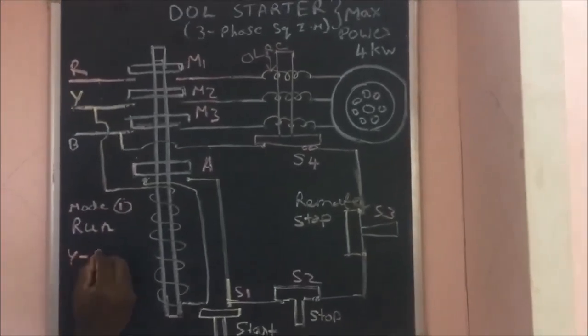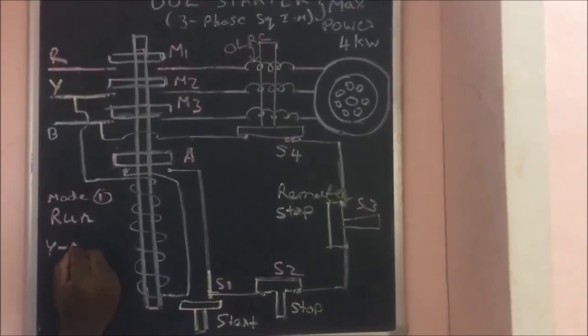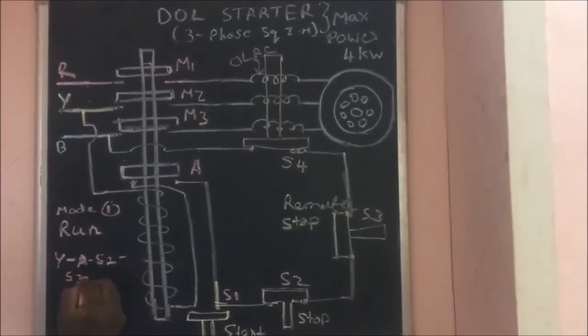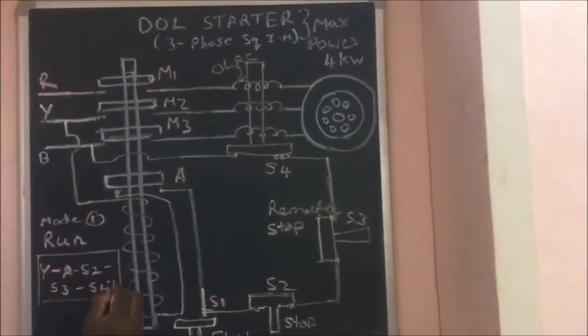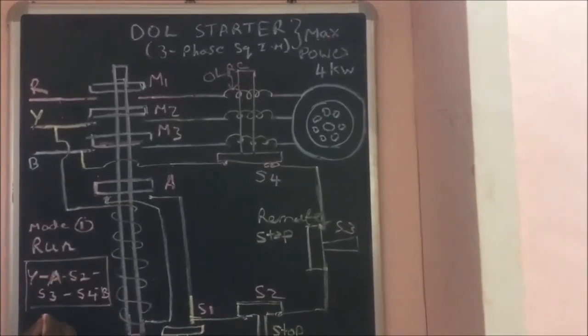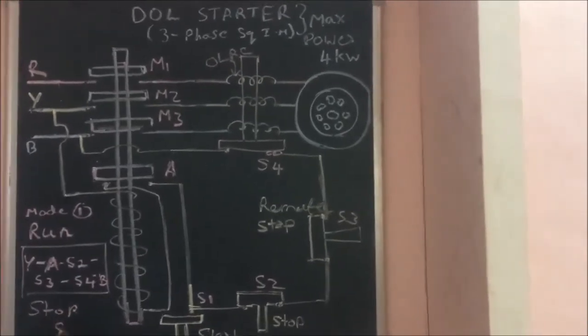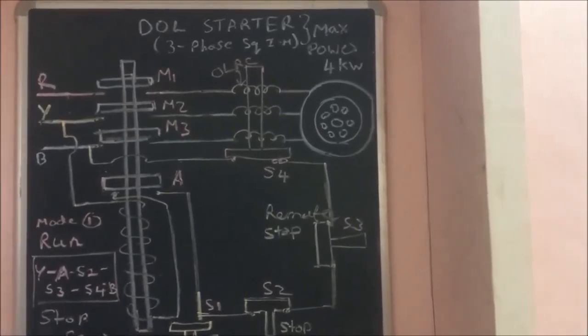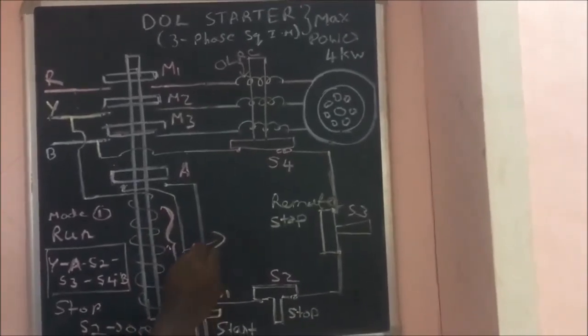In the direct online starter, starting takes place as follows. S1 is the starting or push button — it is the green button. When you push the button, it will close and make contact, and current will flow through Y-phase, A, S2, S3, S4, and finish in B-phase. The under-voltage release coil will become magnetized.